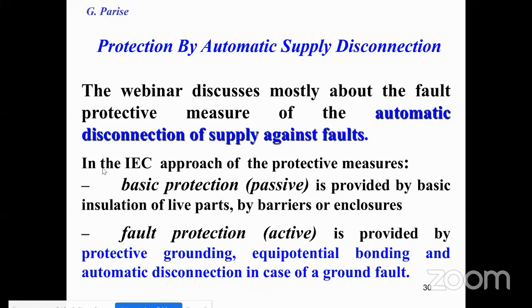If I can touch a conductor, this conductor has to be double insulated. If the conductor is protected in the walls or in a duct, double insulation may not be used. But if I can touch it directly, it is necessary to have this basic protection. Direct contact has to be avoided in a passive way. Indirect contact is admissible, it is foreseen, but only in fault condition. And so the active fault protection is provided by protective grounding, equipotential bonding, and automatic disconnection in case of ground fault.